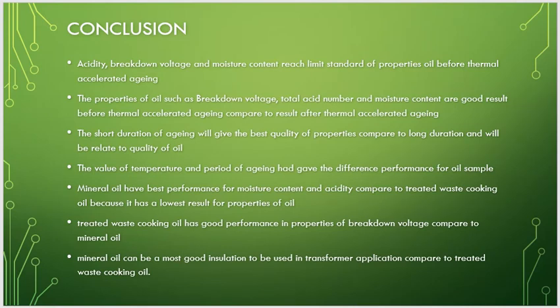And lastly, for the conclusion, acidity, breakdown voltage, and moisture content are limit standards of oil properties before thermal accelerated aging. The properties of oil such as breakdown voltage, total acid number, and moisture content give good results before thermal accelerated aging compared to the results after. The short duration of aging will give the best quality of properties compared to long duration, and will be related to the quality of the oil. The value of temperature and period of aging have given different performance for the oil samples.